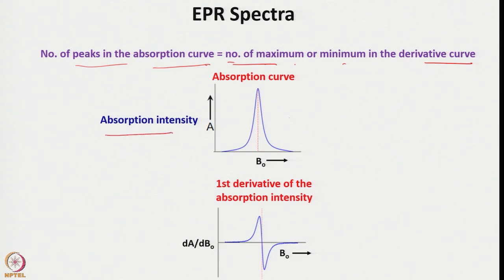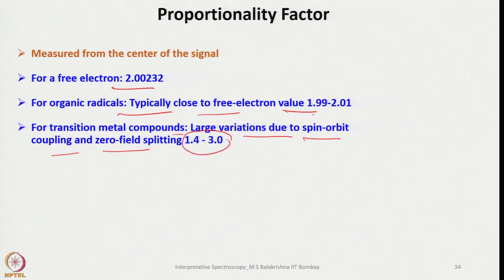The absorption intensity plotted as A versus B₀ gives the absorption curve. The first derivative of the absorption intensity gives the derivative curve, which is what is typically displayed in EPR spectra. The G factor is measured from the center of the signal: for a free electron G = 2.00232, for organic radicals it is between 1.99 and 2.01, and for transition metal compounds the range is 1.4 to 3.0 due to spin-orbit coupling and zero-field splitting.